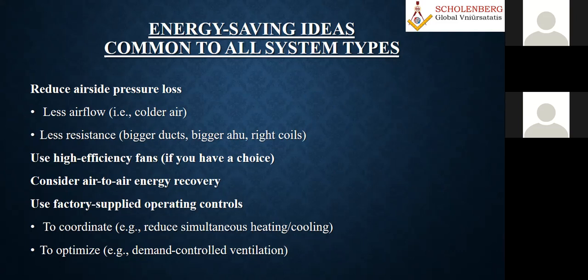What kind of fan you have to go for, you can always compromise. Is it a centrifugal flow or axial flow fan, and how much CFM you want to handle, it all depends upon the application. Noise is not a main consideration. Accordingly, you can go, and then fan efficiency also, because fan technology is also improving, and now VFDs, variable frequency drives. This technology was maybe only 20 years back, and it is now evolving so much more advanced.